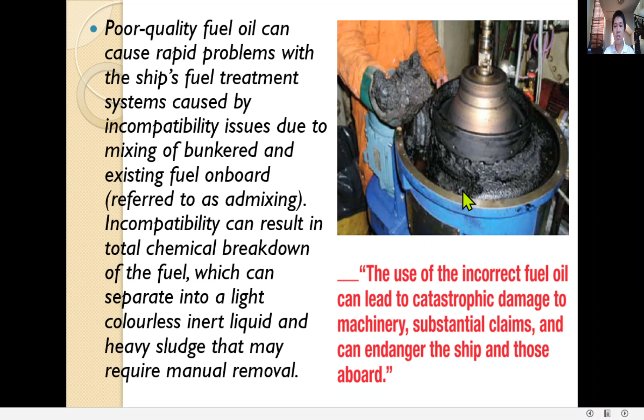What happened when I was a second engineer on board, we assigned the wiper and the oiler every 30 minutes to open the bowl hood of the centrifugal purifier to remove this sludge accumulation. So every 30 minutes, they had to stop the purifier, open the bowl hood and remove the sludge accumulation. That is how the poor quality of fuel can affect the fuel oil treatment, which is the centrifugal purifier.